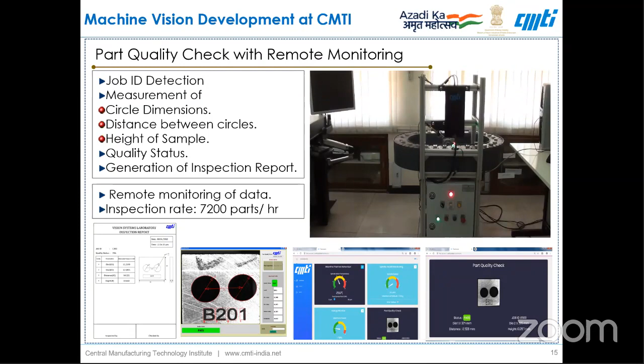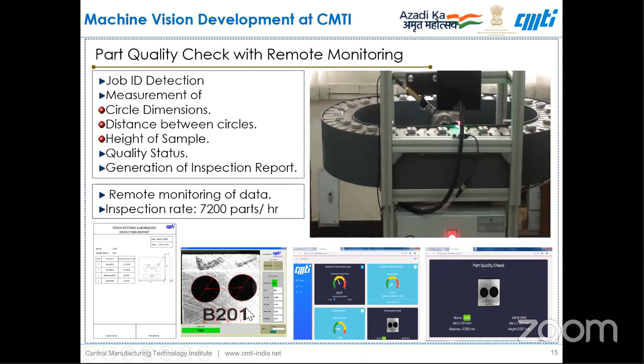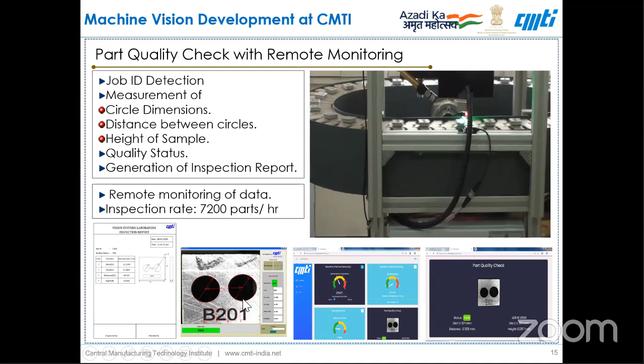The component has 2 holes. It also has some characters engraved on it. Here we are measuring the circle dimensions and the distance between the 2 circles. We are inspecting the label which is engraved on the sample, and also measuring the height. Height is something which we cannot measure with a 2D measurement system; it requires 3D. That is the reason we have introduced a laser into the inspection system that measures the height of the sample.